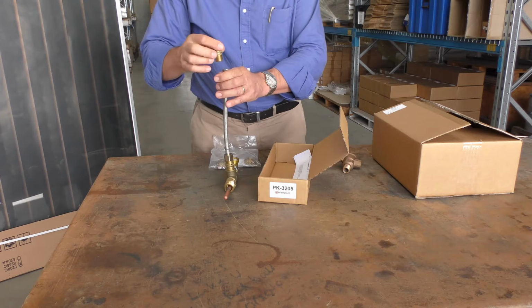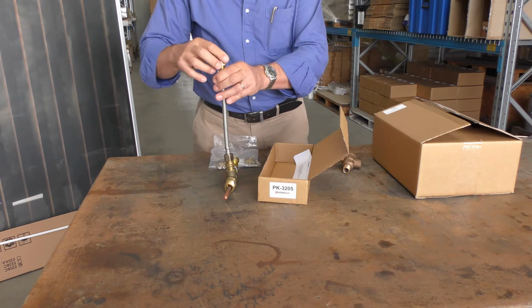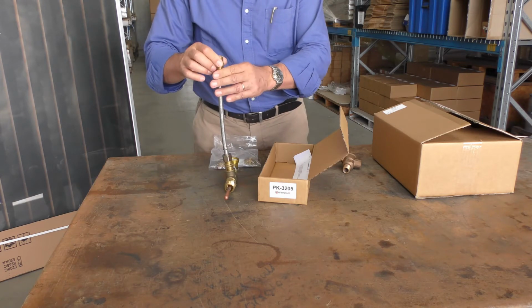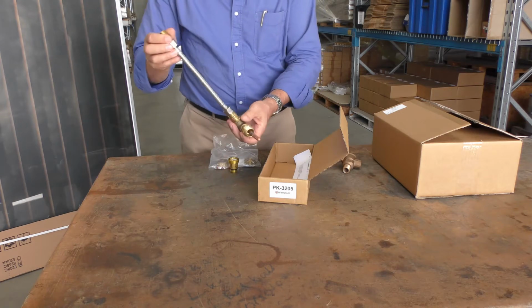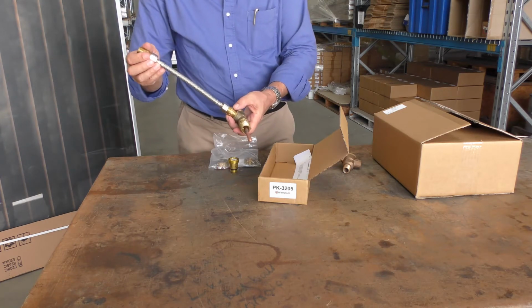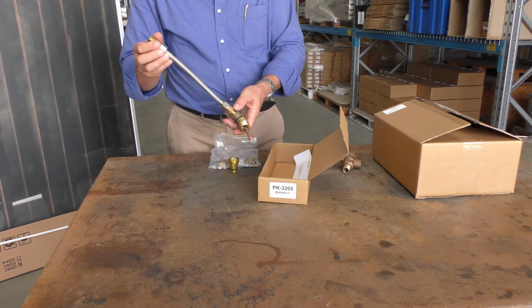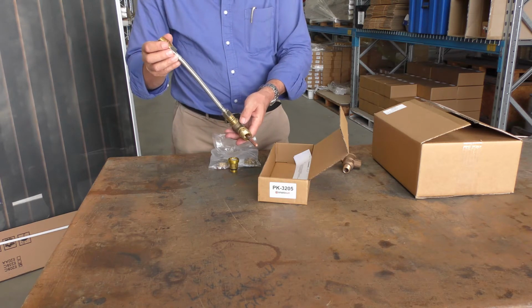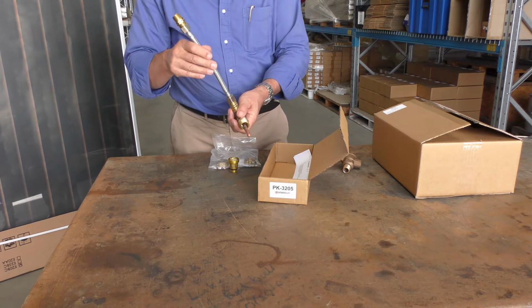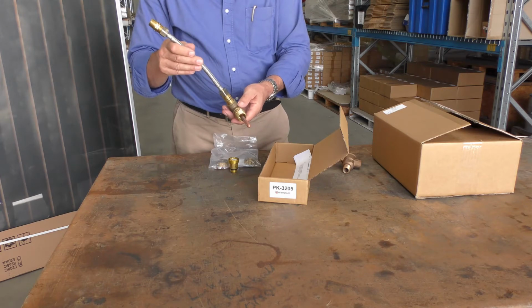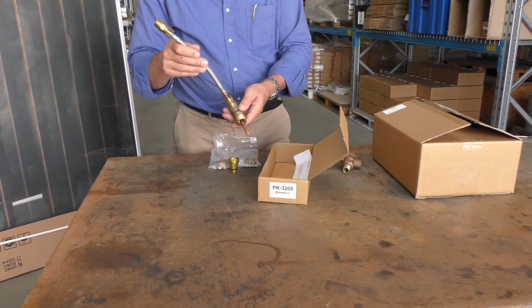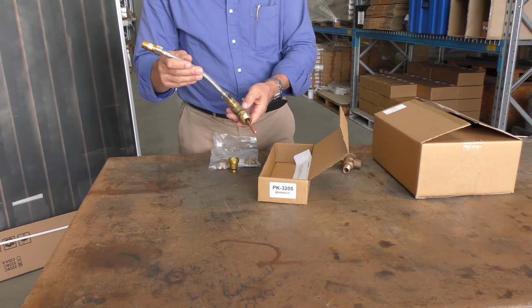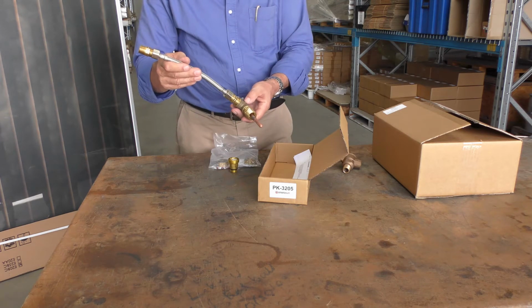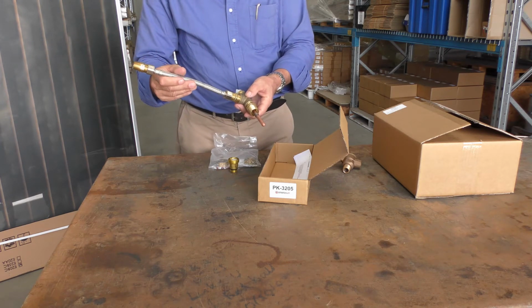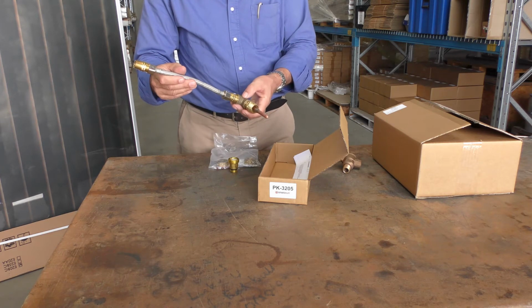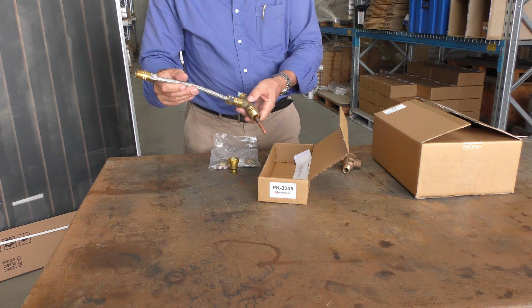Keep in mind, these hoses - and I do get this question sometimes - are they suitable for this temperature? At the bottom of the collector and the bottom of the tank, we don't usually achieve any greater than 70 degrees C, which is the maximum set point. That's a normal hot water temperature, and this is more than adequate to handle it. We've been using these for over 15, 17 years now, and they've been more than adequate - very rarely do we see any returns or problems with these items.